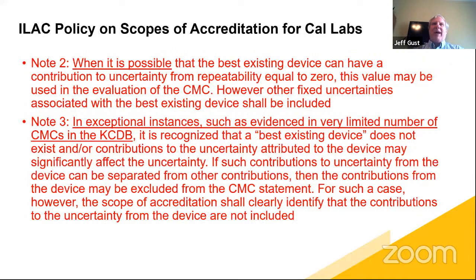Now, the laboratory is violating P14 by reporting an uncertainty that is smaller than what they're accredited to. That happens all the time. So we made the note in there that when it is possible that the best existing device can have a contribution to uncertainty from repeatability equal to 0, then let's go ahead and use this in the evaluation of the CMC. If it is possible, go ahead and do it. However, other fixed uncertainties associated with the best existing device shall be included. So again, it does give you some leeway of, okay, I may not be getting a 0 standard deviation for my repeatability test today, but it's very possible with this device I could. Then let's just put that in the scope so we don't keep shooting ourselves in the foot with this problem.